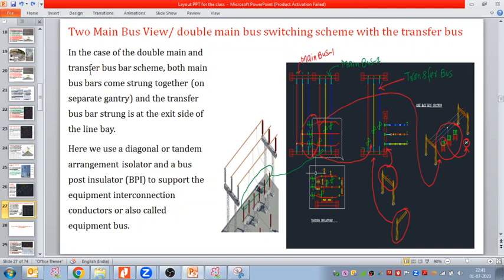So in the case of the double main and transfer bus bar scheme, both main bus bars are strung together, and the transfer bus bar is strung at the exit side of the line bay. Here we use a diagonal or tandem arrangement of isolators and a bus post insulator or post insulator to support the equipment interconnection. Conductors are also called the equipment bus. I think I have covered this point during the SLD as well. Am I clear? You have told us when the tandem arrangement has to be used for isolators. Yes, so when the tandem arrangement is used, we already covered that during the SLD bus bar scheme as well.